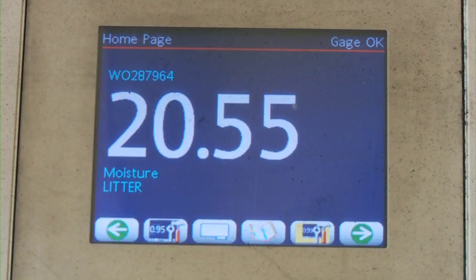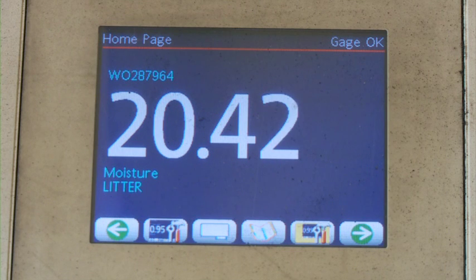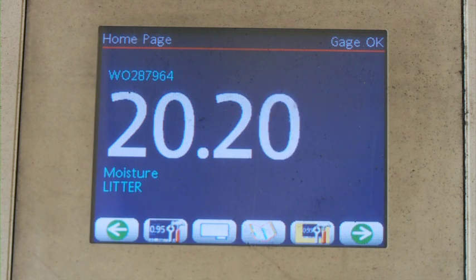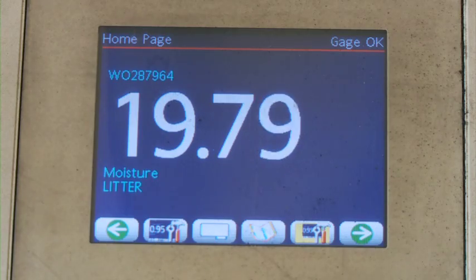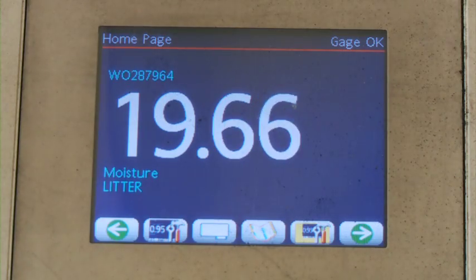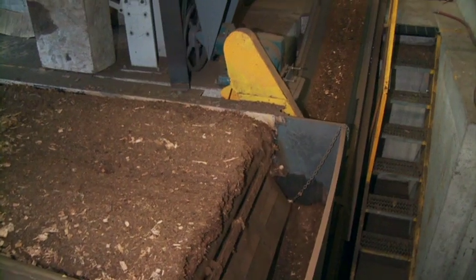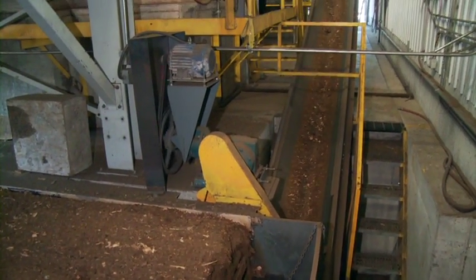Most waste materials contain moisture, with some as high as 80%. If the waste fuel has a moisture content above 10 to 15%, a dryer should be considered in the system design. Next, the material is weighed on a weigh belt conveyor before entering the gasifier.